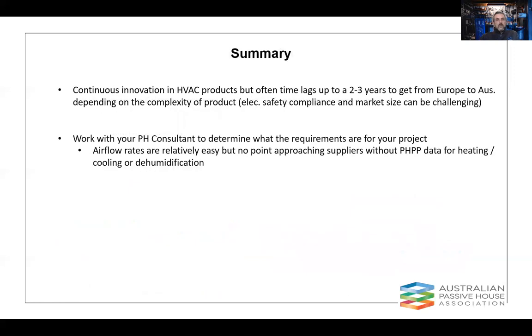So in summary, there's been quite a bit of innovation continuing in HVAC products. These are typically being driven out of Europe, maybe to some extent in Asia, but they are taking some time to get from Europe to Australia. And that's related to complexity of product a little bit, and that might be about electrical safety compliance. So any items that are considered not low voltage, so anything more than about 50 volts, we'll call high voltage or non-low voltage product. And this is for Australian markets specifically. This requires a fair bit of testing to make sure it's electrically safe.